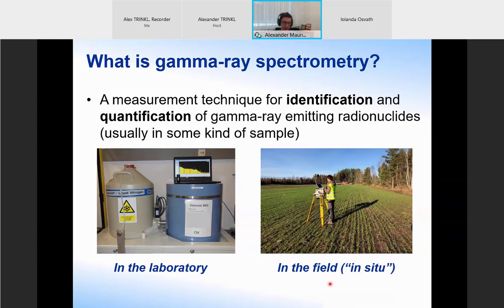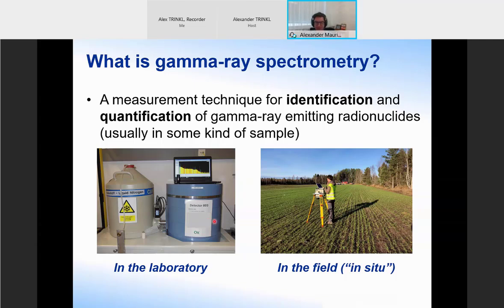However, whereas in the lab you might take a sample from somewhere and bring it to the detector, if you do it in the field, of course, you're doing the opposite. You're taking the detector and bringing it out to the sample, or to the field where you want to do a measurement. On this picture, the actual detector is hidden within this lead shielding, which you'll see here, kind of bluish. But if you had, let's say, supervision and could look inside, it might look something like this. You have a detector inside here and maybe a sample which you are measuring on that detector. So the sample is packed in a plastic bag so that it doesn't contaminate our detector.